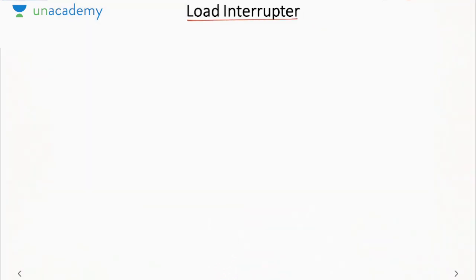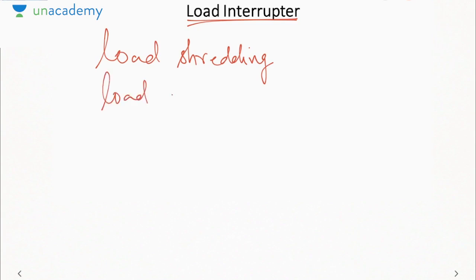Next type of switch is your load interrupter. Now what happens is, whenever there is overloading in the system, then also there will be high current flowing. That is also an undesirable condition. So what does the load interrupter do? It will disconnect the additional load in the system so that the load is less than the rated value. Because load must never exceed the rated value, otherwise there will be high current and damage to the system. So it is used for load shedding, okay, to shed the load, or it is also called load curtailment, so that there is no overloading in the system.